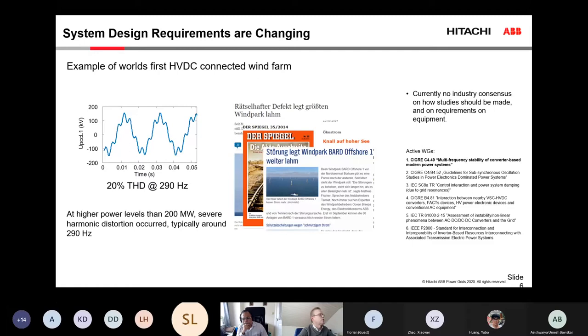And when we had around half of the wind turbines online, we started measuring this type of grid voltage. I will switch to my pointer. So as you see here, this is supposedly a sinusoidal 50 hertz voltage. But on top of that, there is about 20% THD of not exactly a fifth or seventh harmonic, but rather an interharmonic at around 290 hertz.